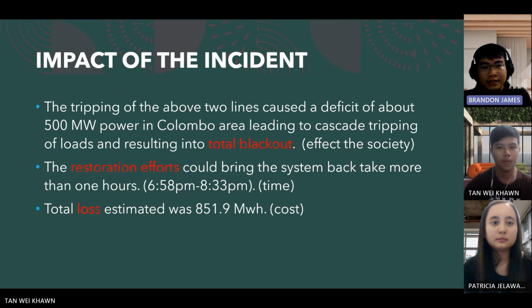And for the impact of the incident, the tripping of the above two lines caused a deficit of about 500 megawatt power in the Colombo area, leading to cascade tripping of loads and resulting in total blackout. This affected society. The restoration effort to bring the system back took more than 1 hour, from 6:58 p.m. to 8:33 p.m. And the total loss estimate was 851.9 megawatt hour.